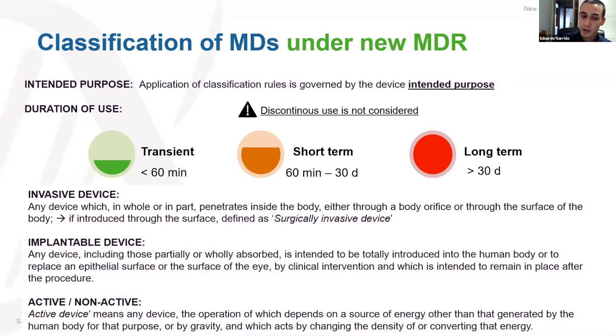You've got to analyze if your device is implantable or not, and you've got to decide if it's active or not. What does it mean if it's active or not? A device is considered active when it relies on a source of energy other than that generated by the body or gravity of the patient.